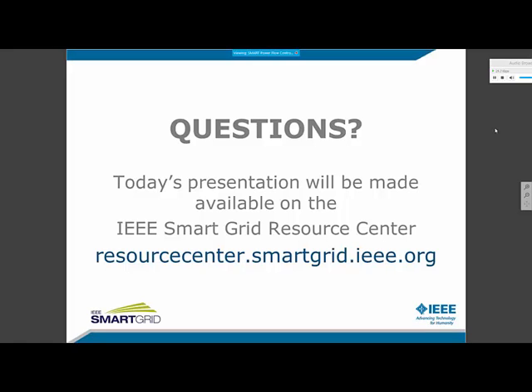Are there solutions presently? Well, that is also one topic of discussion, that all the inverters that we have have very low inertia. As I showed you, the response time is 2 milliseconds. That was a 100 millihertz step. Yeah, one would think that inverters may not be all that useful in a power grid, because the power grid is used to having inertia. But with intelligent control of an inverter, you can make it look like a machine. I mean, we do that routinely. We had a machine that we used in a test, but recently we replaced that machine with an inverter with intelligent control. That inverter looks just like a machine. So look at the Power Electronics magazine in the last few months or so.